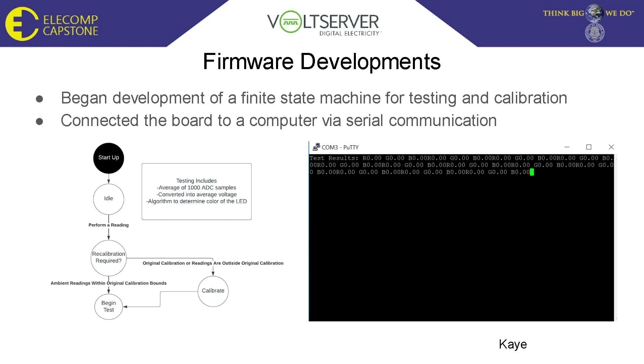When called upon for another test, it will take a reading of the ambient light in the room, and if it is outside an acceptable range of error, it will perform a recalibration before testing. In order to send and receive commands, we would be using serial communication through UART. I was able to set up reading and writing to the UART through PuTTY, as shown in the screenshot of the terminal on the right.